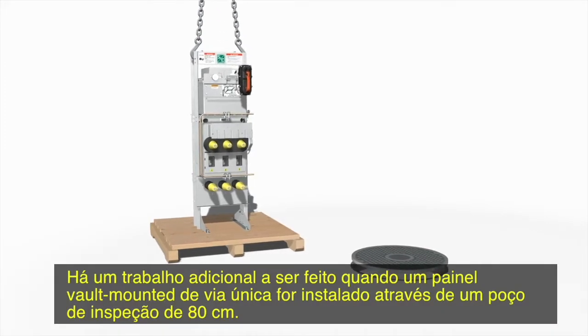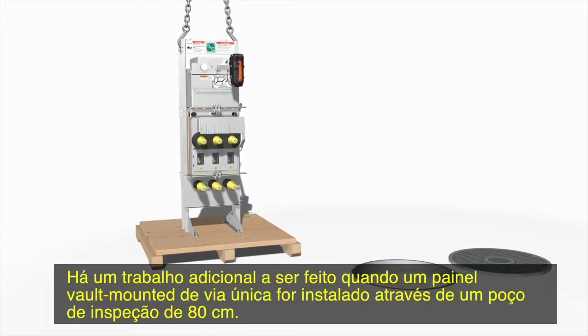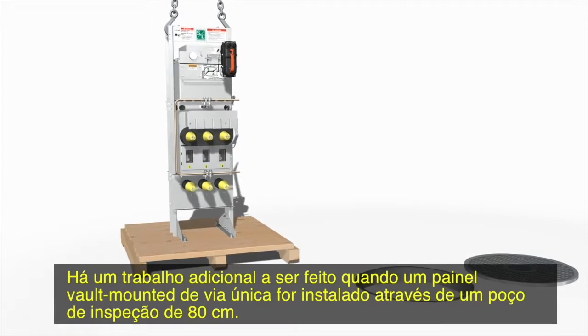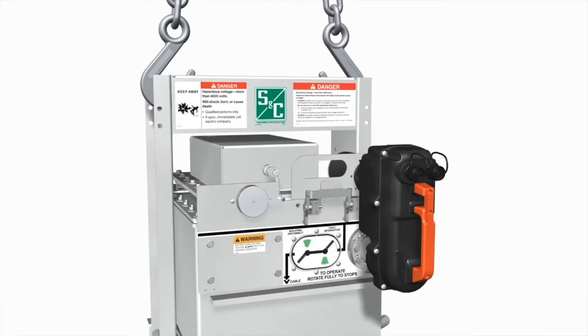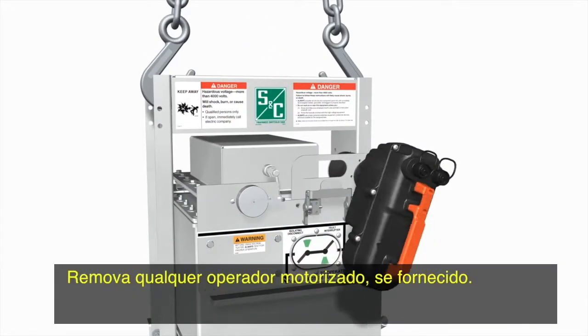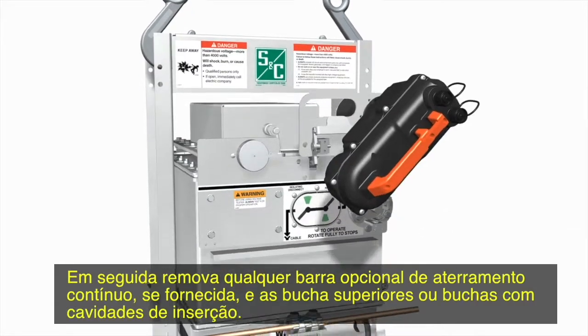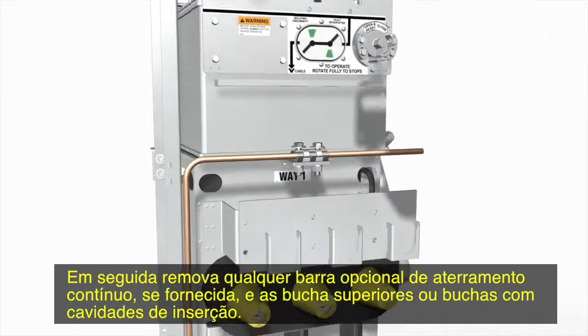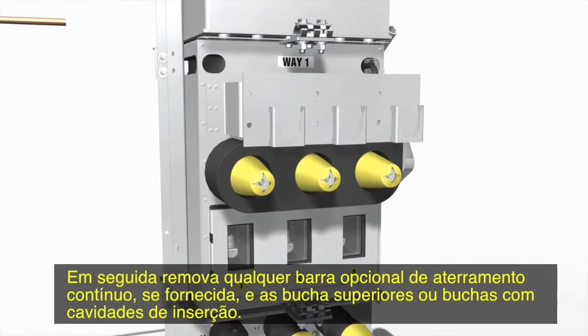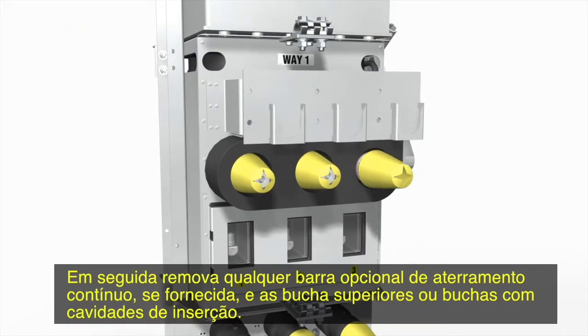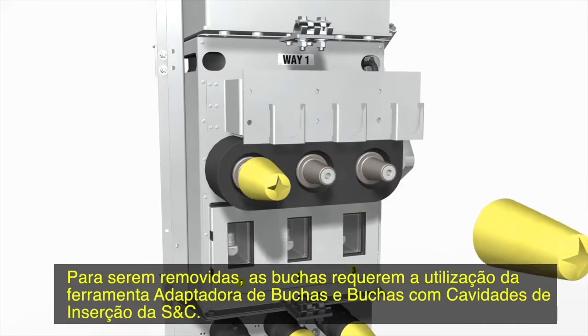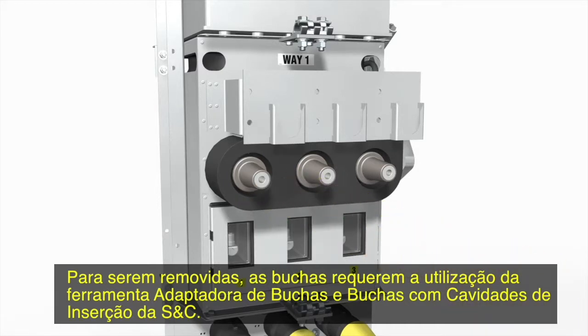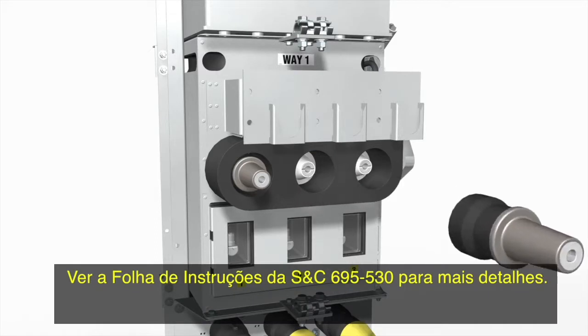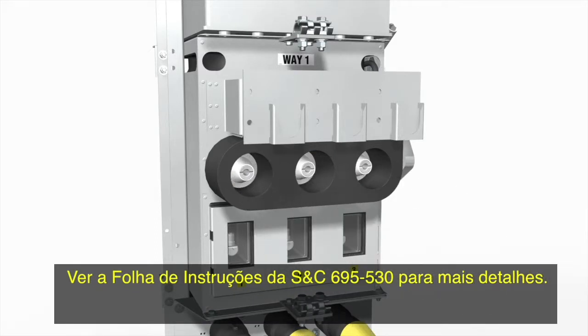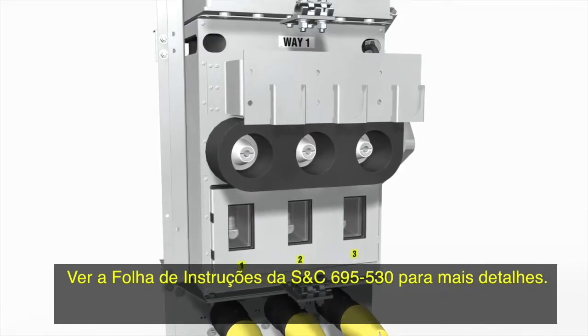There's more work to be done when installing single-way vault-mounted switchgear through a 31.5-inch manhole. Remove any motor operators if supplied. Then, remove any optional continuous ground bus if supplied, and the upper bushings or bushing well adapters. The bushings require the S&C bushing and bushing well adapter assembly tool to remove. See S&C instruction sheet 695-530 for details.